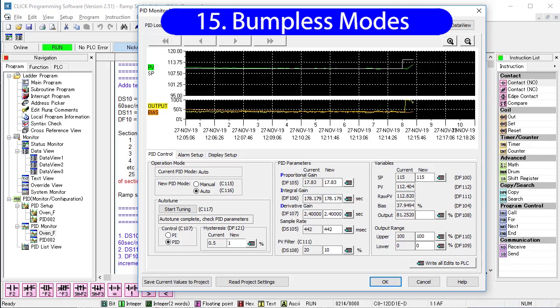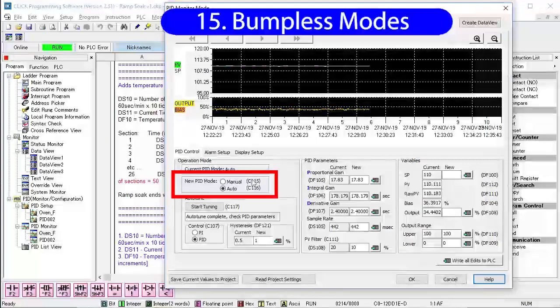That's what bumpless mode is for. It forces the set point to whatever the process variable is so there is no sudden bump in output which allows you to switch to auto mode without having to worry about the machine going crazy.